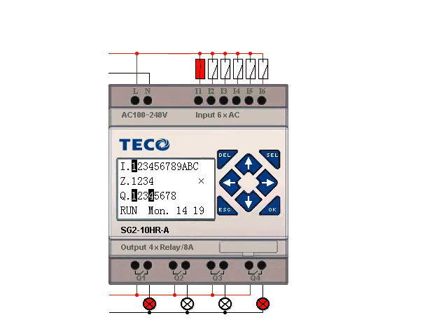So, as you can see, it's loading station number 1 again, and that time it's cleaning the filter. So let's see how often it does that. It cleaned it that time, and it won't do it this time. So you can see that it's set every other load to clean the filter, and that's how we set it up. Always here, you can see all the different highlighted outputs and inputs. So you can see the material switch is on, and the no load, and now material 1. This is how you can troubleshoot the unit during normal production. We'll turn this off. The no load alarm comes off.